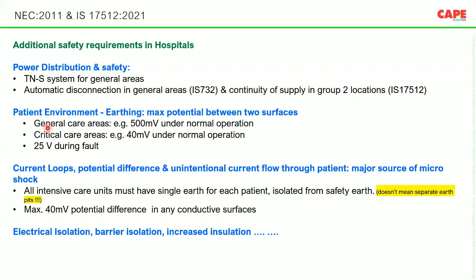Patient environment. In general care areas, 500 millivolt under normal condition. The potential difference between two simultaneously accessible metallic parts must be lesser than 500 millivolt in general care areas, and in critical care areas, the voltage between two simultaneously accessible parts should be lesser than 40 millivolt under normal condition. This 500 and 40 is under normal condition. So the supplementary equipotential bonding must be very, very efficient to reduce the potential difference lesser than these.